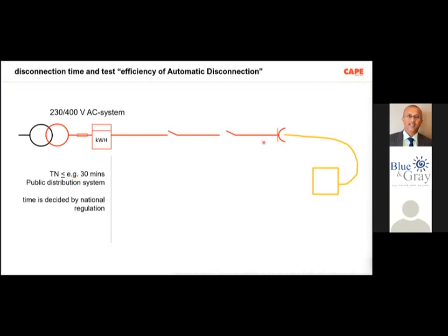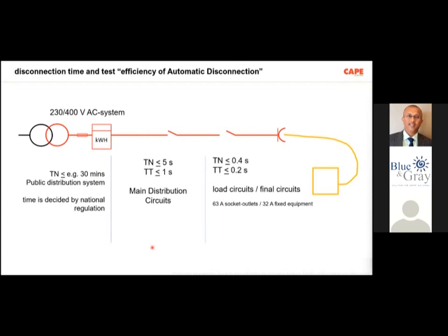Then we come into your electrical installation. For the fixed part of the electrical installation, the main distribution circuits, in case of a TN system, the disconnection time is 5 seconds, and in case of a TT system, less than or equal to 1 second. And for the final circuits, the load circuits, especially up to 63 amps with socket outlet devices and 32 amps fixed equipment, the recommended disconnection time is 0.4 seconds in a TN system and 0.2 seconds in a TT system.